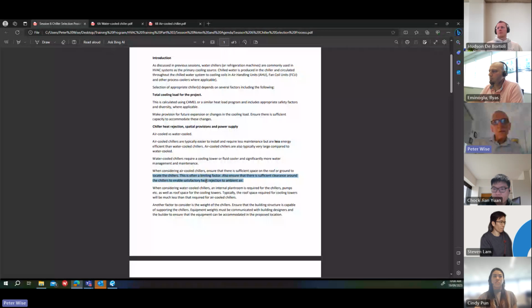Typically, the chiller is located in a plant room within the building. You can build an enclosure on the roof if you haven't got a plant room available and you want to use a water-cooled chiller. You could put it into an enclosure on the roof. You know, it's an option, but it's very rare to do that. I have seen it done. You know, it's certainly an option. And the roof space required for cooling towers is normally much less than that required for air-cooled chillers.